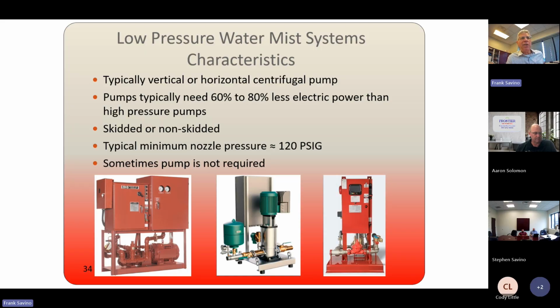You can do skidded or not skidded. These are all skidded assemblies. What that means is that on the depiction all the way to the left, you've got a horizontal pump and a motor with your fire pump controller. And you've got your jockey pump controller, and then you even have your pre-action control panel, all pre-assembled on one skid. You can do that, or you can have these separate components. You can put your fire alarm control panel and your fire pump controller on the wall, and you can put your fire pump and your motor on a pedestal. So you can go either way on that and treat it just like a regular sprinkler system.